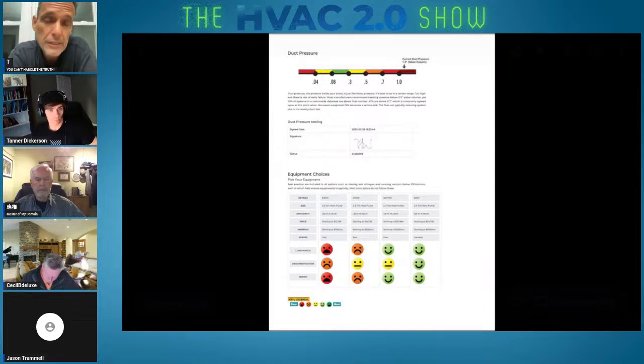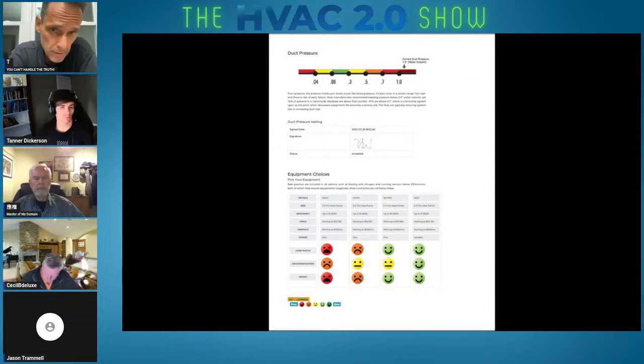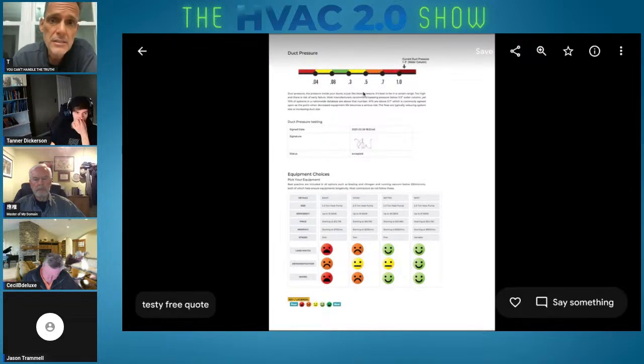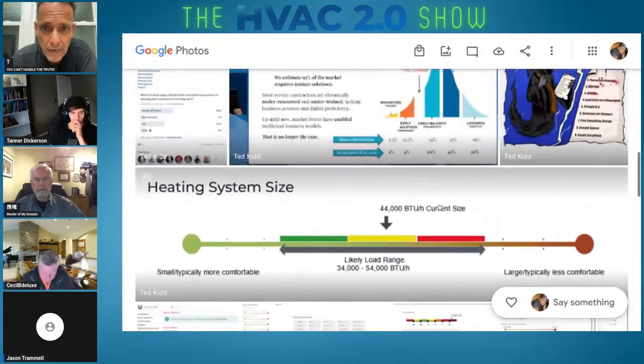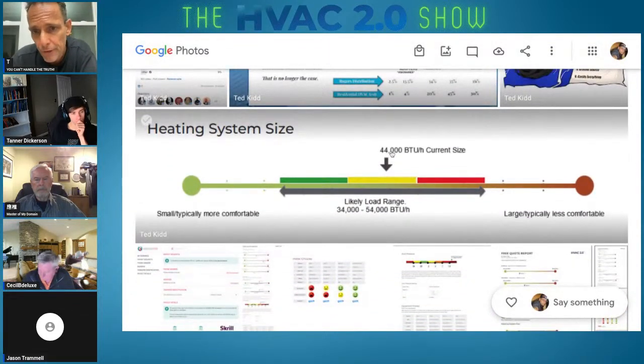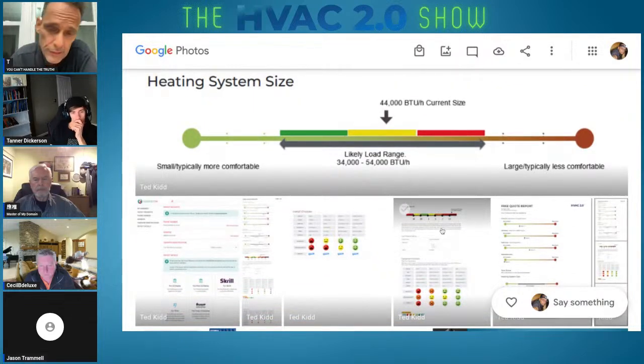Yes. Whereas in this case, since one of the things we do through our approach is offer duct pressure testing, this, when you tie it back to likely load range, helps the homeowner understand where they are. That further helps people understand, oh, at 44,000 BTU, my current equipment is oversized for a good house this size, and the ductwork is undersized to this equipment because of the static pressure.